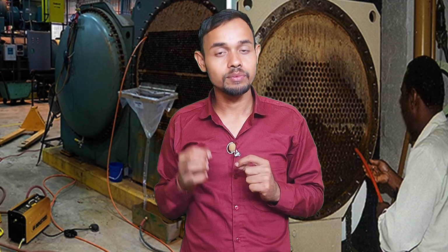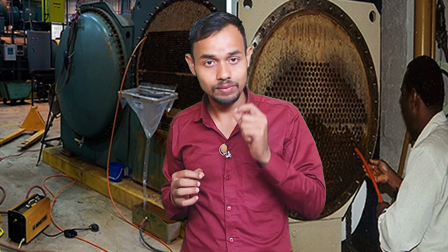First, cooling efficiency drops, second, compressor load doubles, next, electricity bill shoots up, and next, the chiller may even trip. Okay, and the only reliable solution is descaling. Yes, so let's see the simple explanation. What is chiller descaling, friends? Chiller descaling means dissolving and removing hard scale from the condenser, evaporator, or the heat exchanger tubes using chemicals.